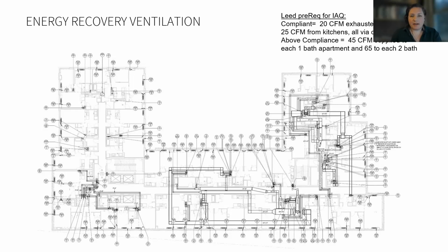In the mechanical plan here, you can see on the 12th floor ductwork, on the right, all the ducts collecting to meet the equipment on the roof directly above. And on the left side of the plan, the risers continue to the roof unit on the top of the tower. Other important considerations in ventilation are making sure you're using high quality filters, so we use MERV 13 or better, and using CAV dampers, which keeps the airflow balanced in a large building, especially important with a lot of stack effect, and making sure you have really good air sealing in your shafts. So we use a product that seals them after they're constructed from the inside.